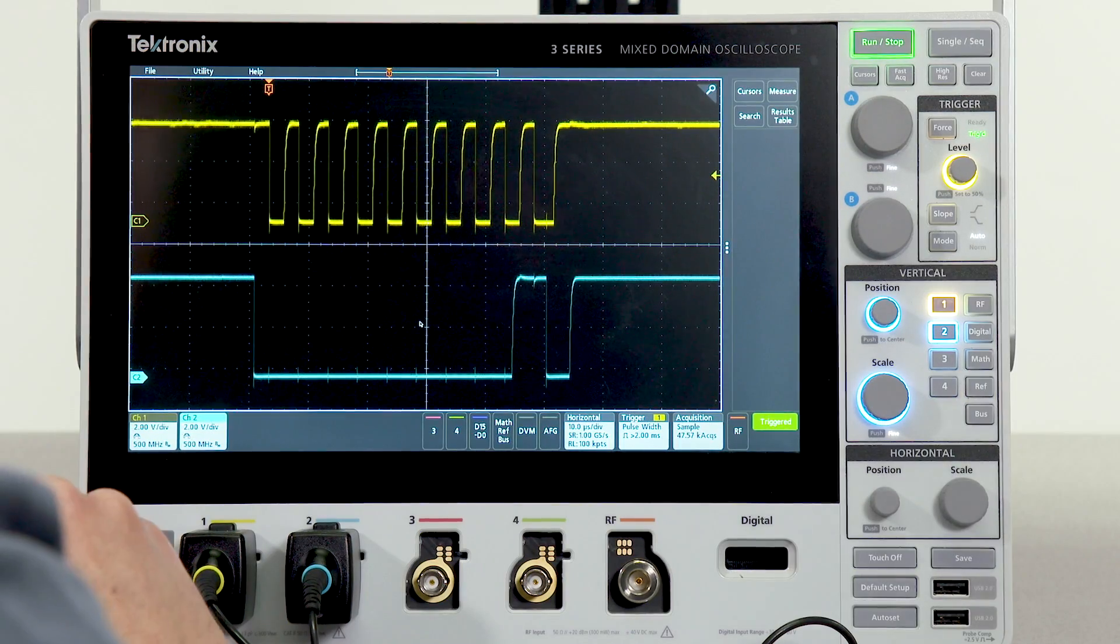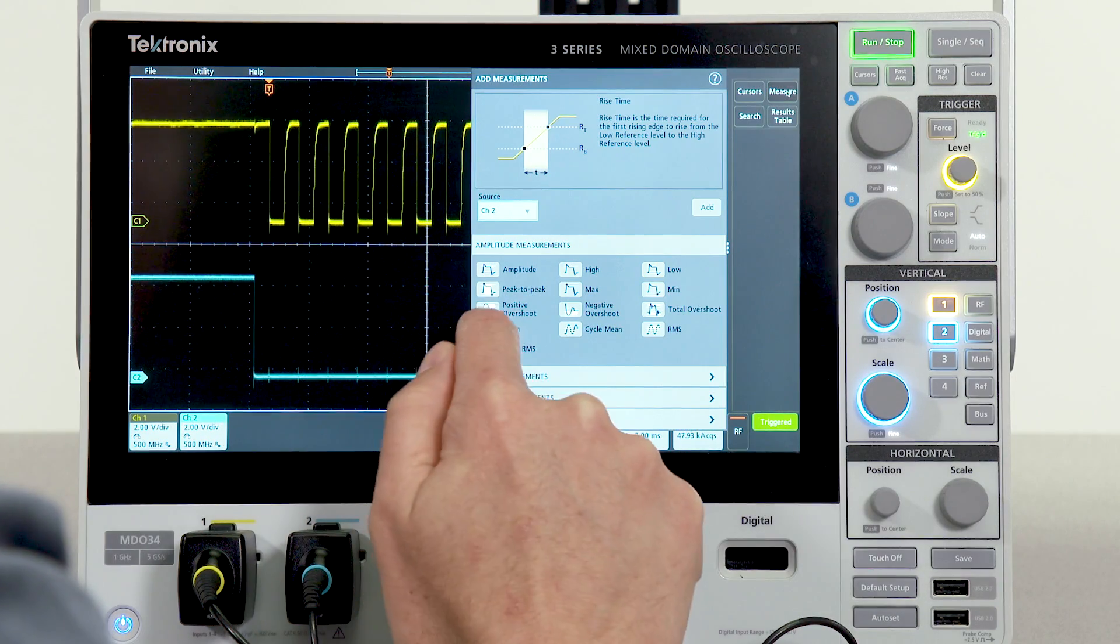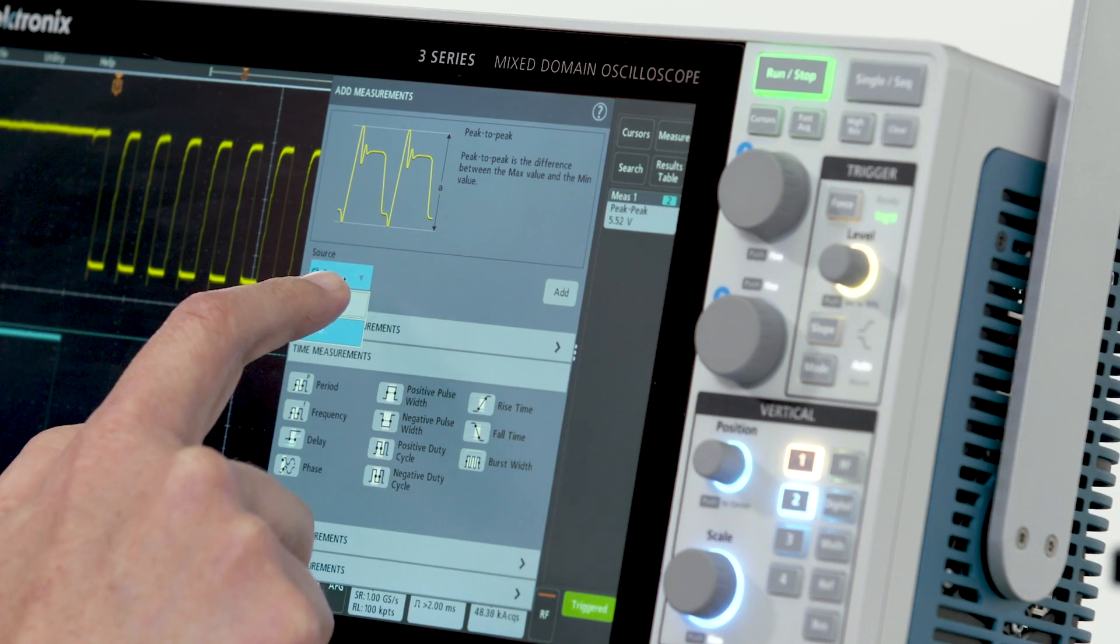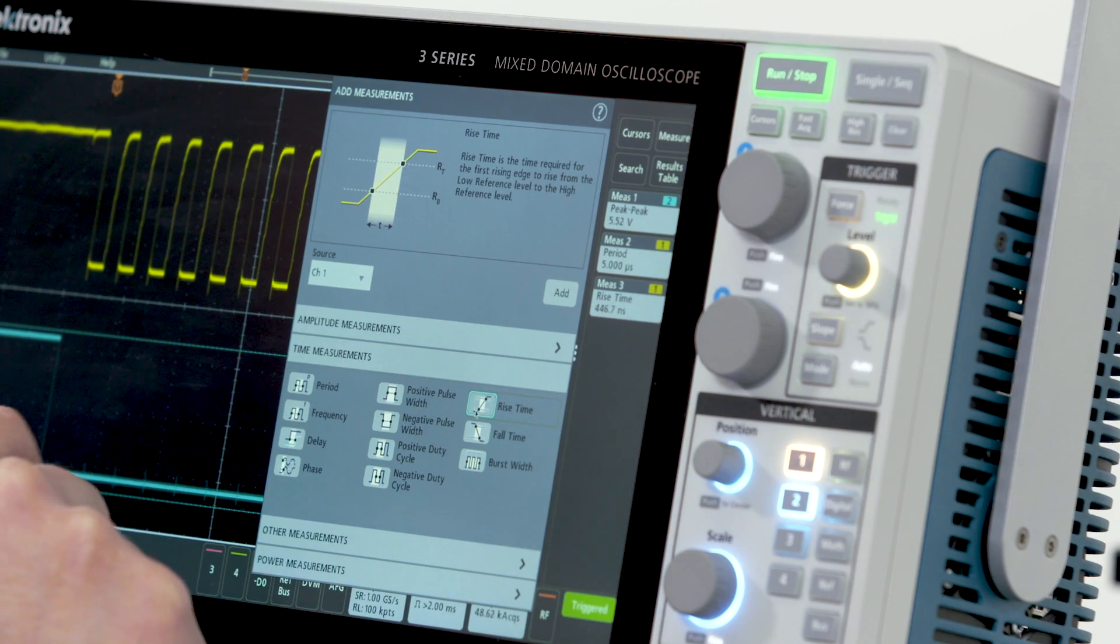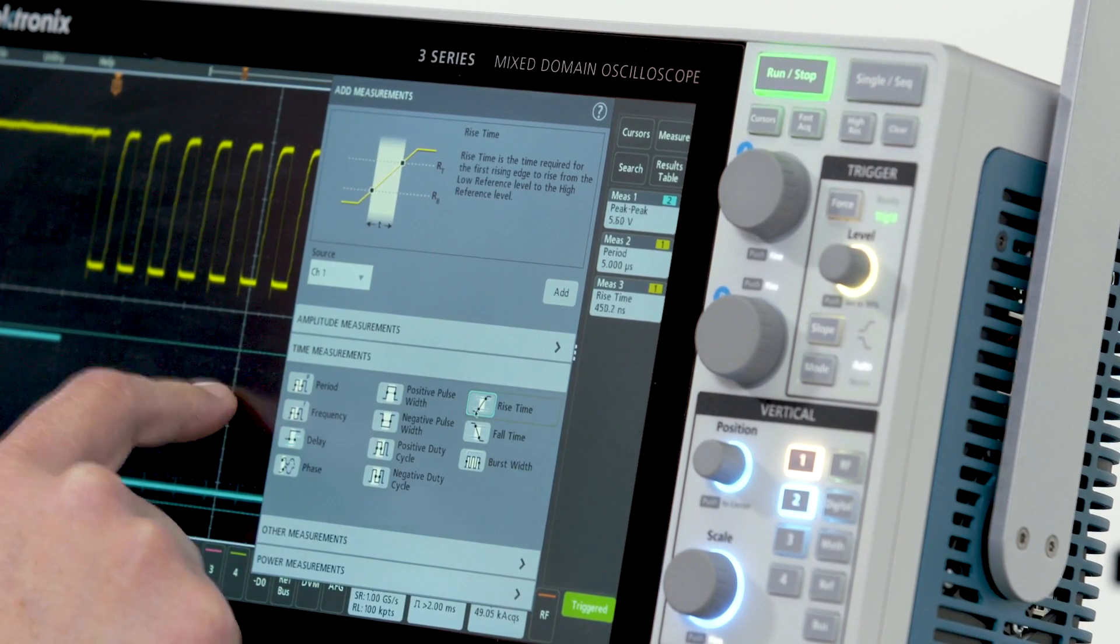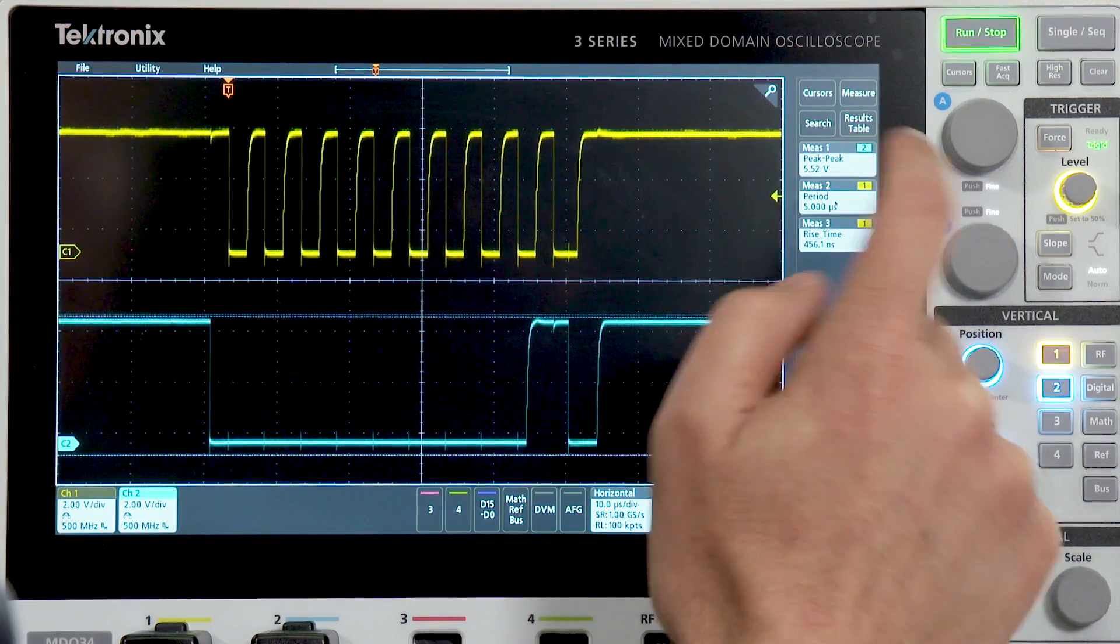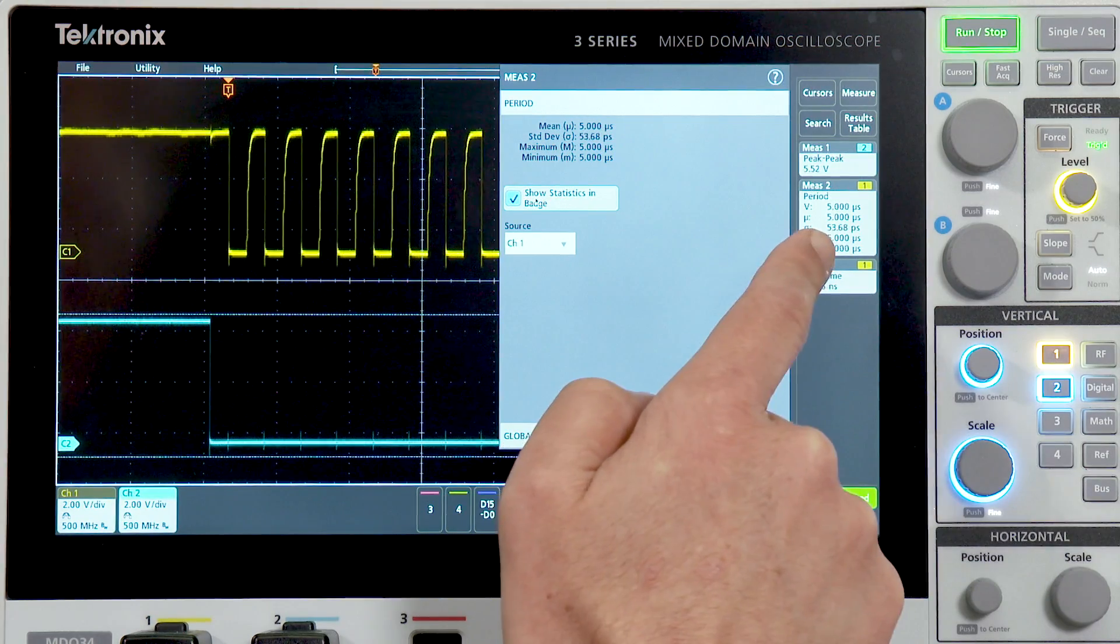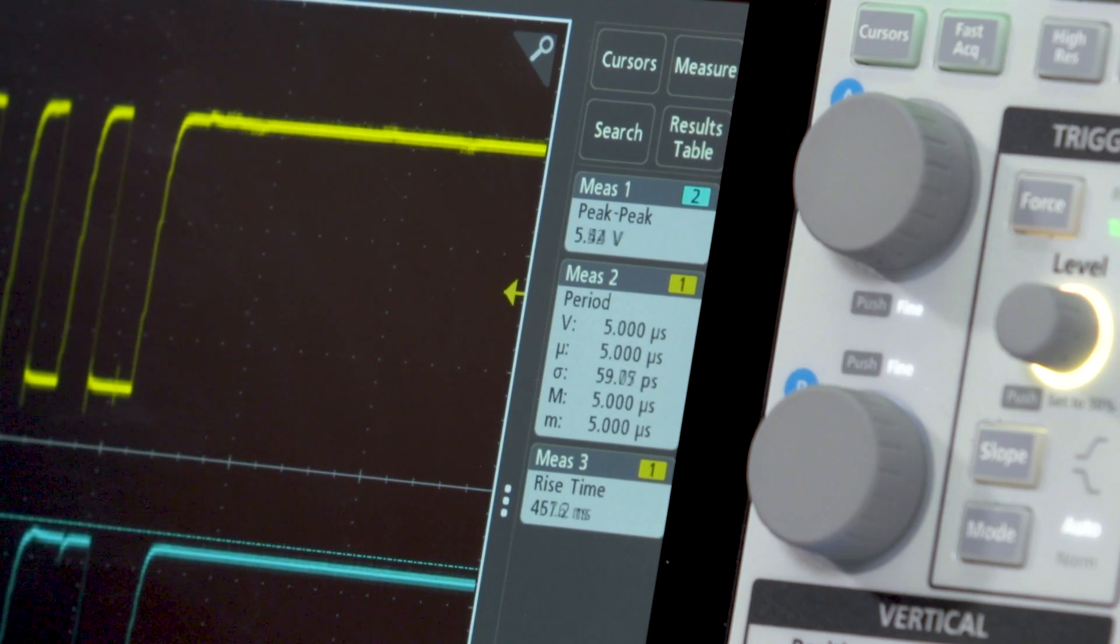Now let's look at some automated measurements. To do this, I'm going to select the measure menu. On channel 2, I'll add a peak to peak measurement. On channel 1, I will add a period measurement and a rise time measurement. Notice that as I add the measurements, each one gets a badge in the results bar. To see how the measurement varies over time, I can double tap on a measurement, select show statistics and badge. And now I can see my mean, standard deviation, maximum and minimum for that measurement.